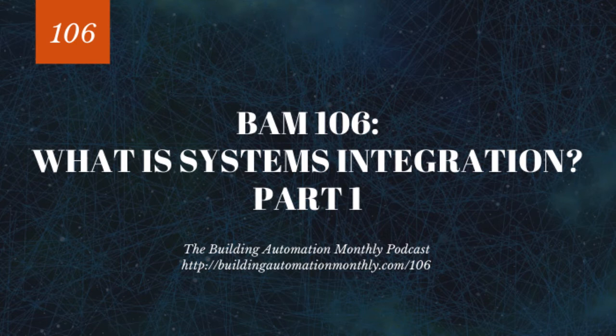And then the third and final thing is that you've got to understand who takes the lead. This is true of almost all protocols. So here's the deal, right? Let's say you have an elevator system or a lighting system. With the elevator system, you're pulling it via Modbus, and you've only got read-only points. Well, in that case, you're pretty safe. You really can't do much damage. You can't go and override the elevator because that's a life safety thing.